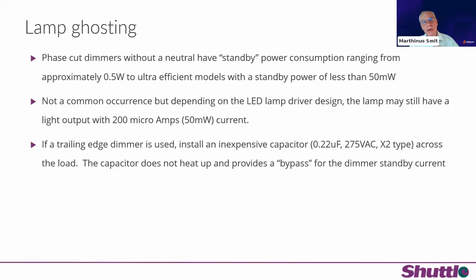Now, a problem which was very common up to about 2018 was lamp ghosting. That's where the lamp stays on when the dimmer is still off. Now, phase cut dimmers without a neutral, which is the most popular type of dimmers in South Africa as well as abroad, typically have a standby power consumption when the dimmer is off of about 0.5 watt, but then you get your ultra efficient models, which bring that standby power down to about 50 milliwatts. And it's incredibly little. It's about 200 microamps maximum.